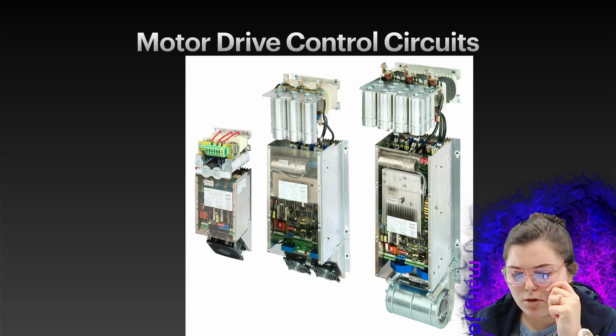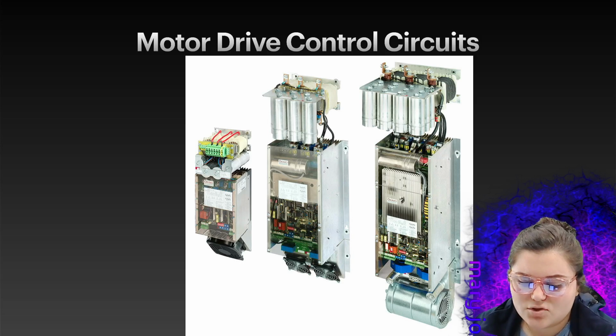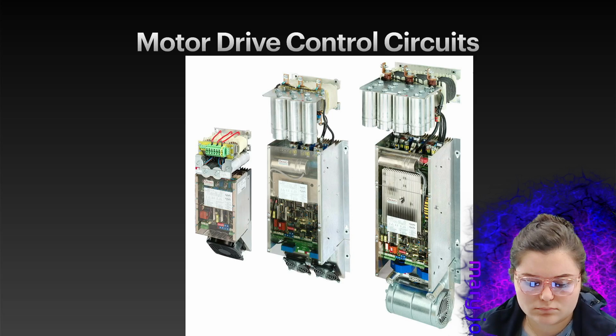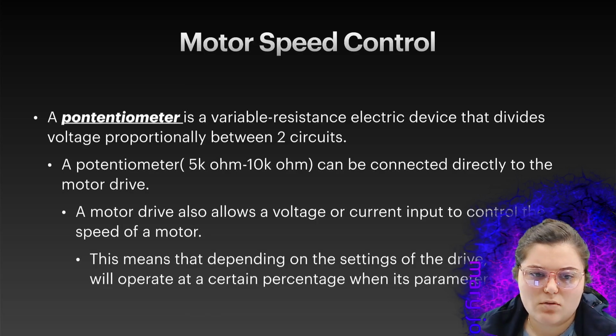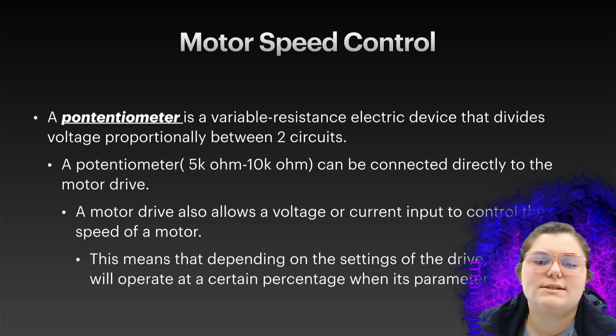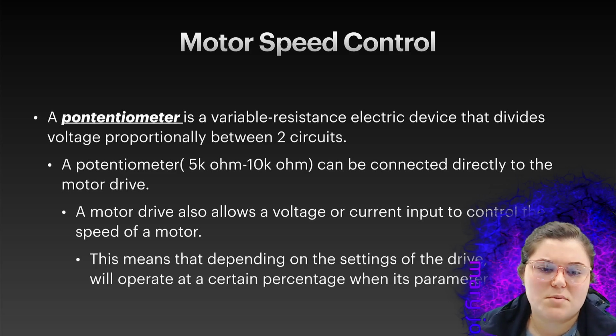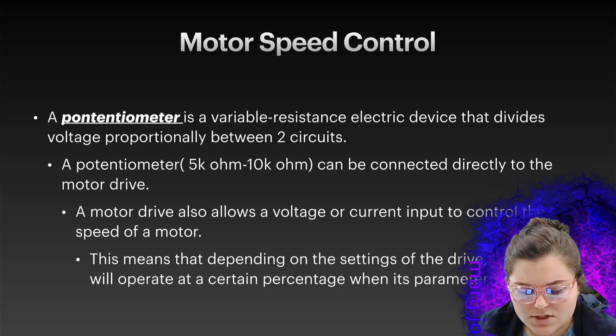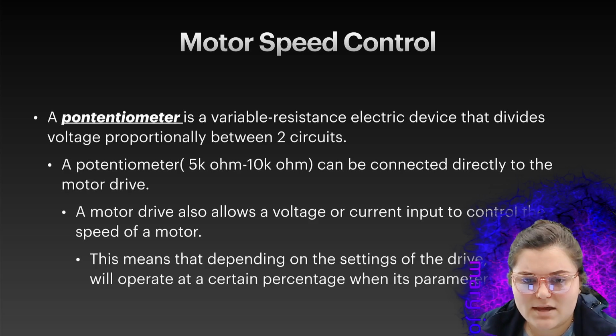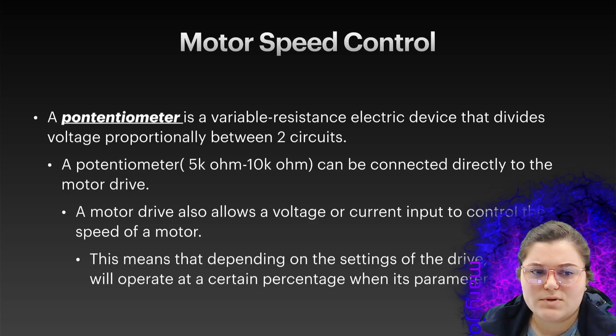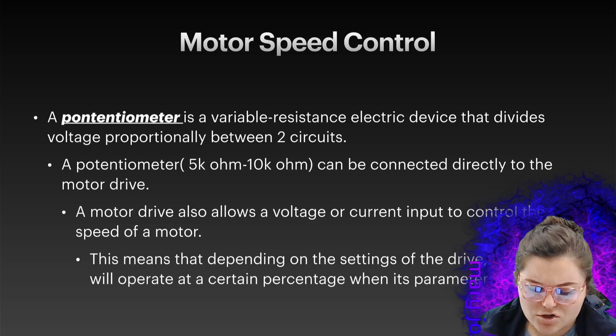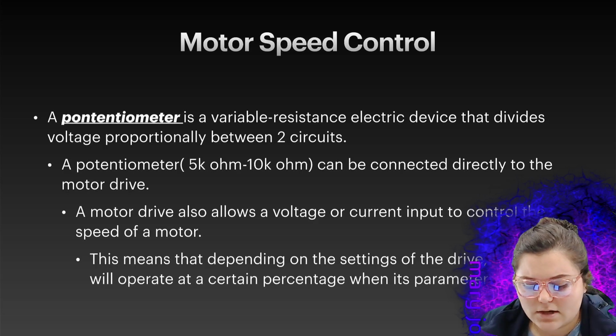A major advantage of using a motor drive instead of a motor starter is that the drive offers different motor speed control. So a motor speed control potentiometer is a variable resistance electric device that divides voltage proportionally between two circuits. A potentiometer, where it's 5K ohms to 10K ohms, can be connected directly to the motor drive. So in our lab, you'll see us connect a potentiometer, and as we twist that potentiometer, it will make the motor go faster or slower depending on the parameters that we put in. A motor drive also allows a voltage or current input to control the speed of a motor. This means that depending on the settings of the drive, the motor will operate at a certain percentage when its parameters are met.